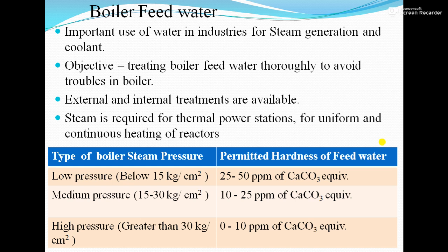Steam is required for thermal power stations for uniform and continuous heating of the reactor. There are three types of boilers: in a low pressure boiler, 25 to 50 ppm of CaCO₃ hardness is permitted; in a medium pressure boiler, 10 to 25 ppm is permitted; and in a high pressure boiler, 0 to 10 ppm of hardness is permitted.